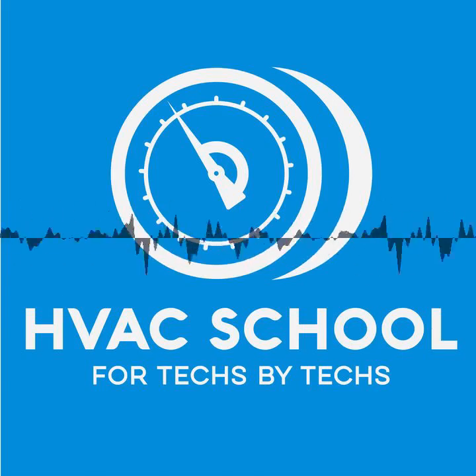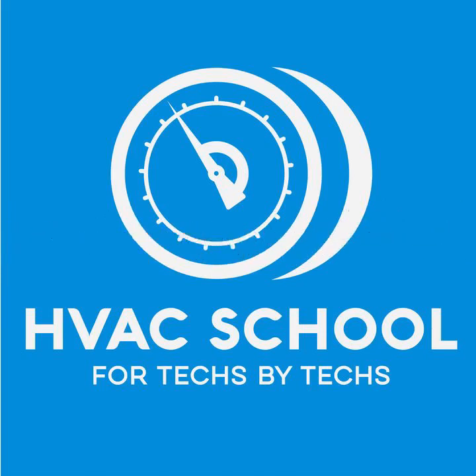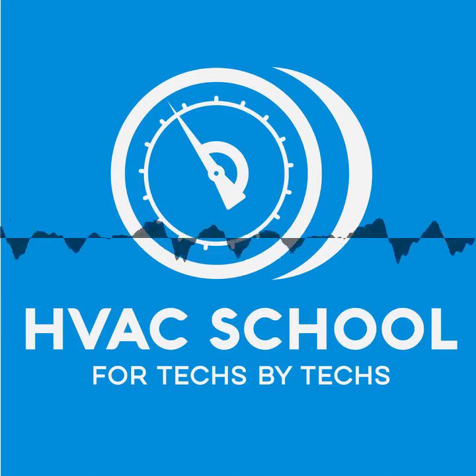Now, if you're using a good flare tool like the RIDGID Spin Flare, and you're getting a really nice burnished face, it's going to leak less than if you're using some of the old style flare tools where they didn't deburr well and you had a lousy flare fitting. The quality of your flare is going to also dictate that, but all of them do leak at some small rate. By RIDGID Spin Flare, he means the Rector Seal ProFit flaring tool.